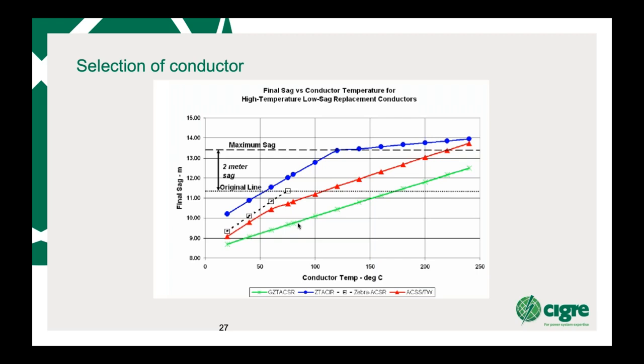Well, you can see this is where the knee point comes in as being very important, because if you've got a ZTACIR, which is the blue line, you're actually going to hit the maximum sag at around 110 degrees, which is not going to give you your current rating, even though the Invar core kicks in at this point and it goes very flat after that. That still doesn't help you. The Zebra that we would normally use on that particular line, templated at around 75 to 80 degrees C. Again, you wouldn't normally run it above that because of annealing problems, and you can't really reach your maximum sag or increase your temperature. So that's a temperature limit.